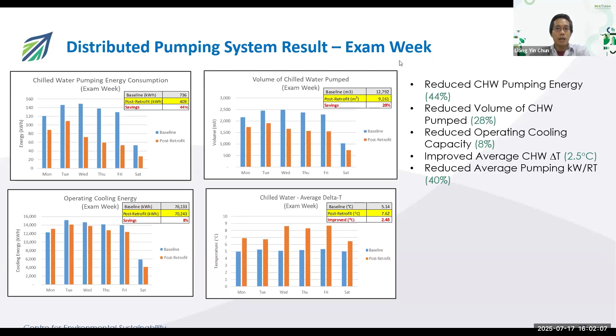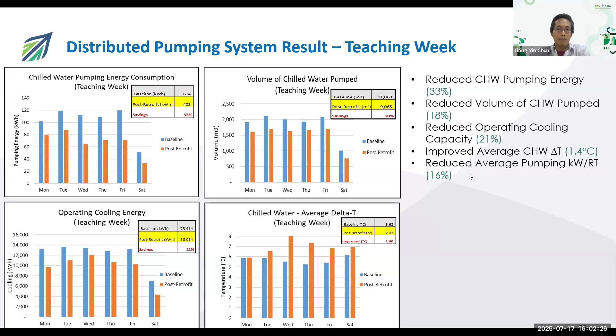And in the teaching week, similarly, we see a 33% reduction in the pumping energy, 18% in the chilled water pump, a reduction of 21% on the cooling capacity, an improvement of the delta T of 1.4 degrees, and a reduction of 16% on the kilowatt per ton for the pumping.